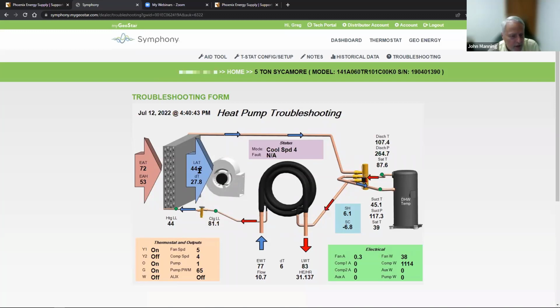Going from 72 to 44, that's a 27.6 degree split, as we call it. It's quite high. If anything, I might increase the airflow to get it closer to 20, 22 degrees. So minor adjustments. We're operating right now on speed 4. The compressor's using 1127 watts. The fan's using 38 watts, which is amazing. It tells us our pump is operating at roughly 65% of full flow. So it's a pretty insightful screen here as to what's going on.